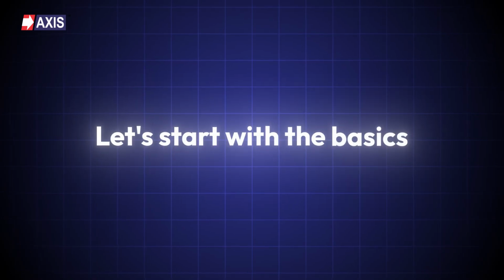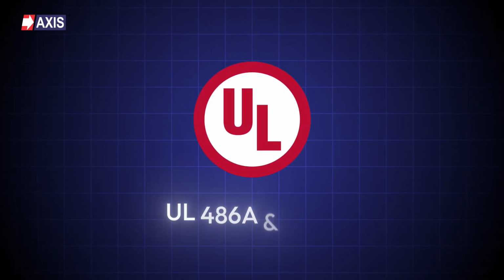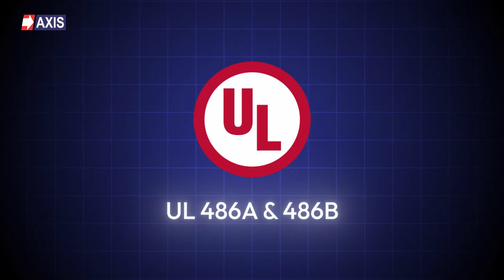But before we compare the two lugs, let's start with the basics. A dual-rated lug is made from a single material like aluminium or aluminium alloy and is tin-plated. It is tested with both copper and aluminium conductors under UL 486A and 486B. If it passes the test, it earns the dual-rated label.